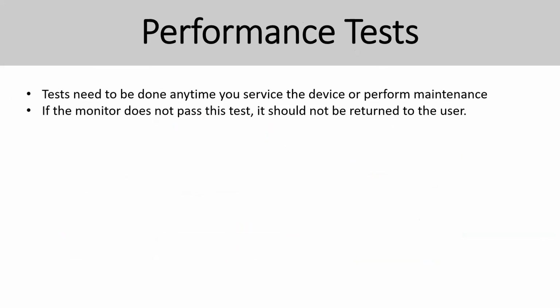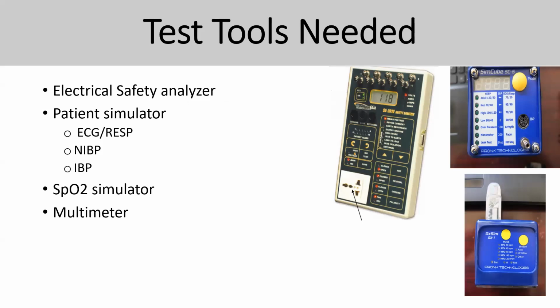So performance test. When you talk about performance test, you are testing according to the standard guideline. So you're going to measure ECG, SpO2, NIBP, whether they are inside the particular range or not. The test tools that you normally need when you do performance tests and electrical safety are a patient simulator, an SpO2 simulator, and an electrical safety analyzer. The electrical safety analyzer is used to test electrical safety of the equipment. Then for performance, you use the patient simulator to check ECG, NIBP, IBP, and SpO2 simulation.